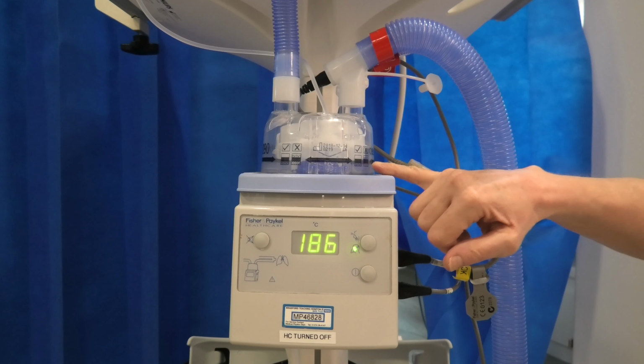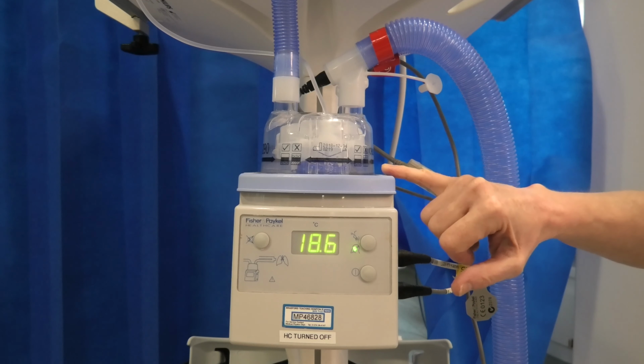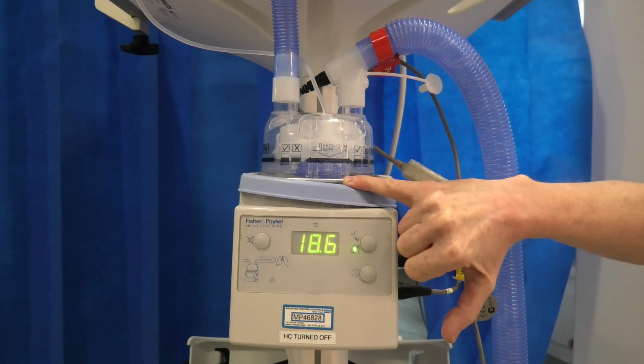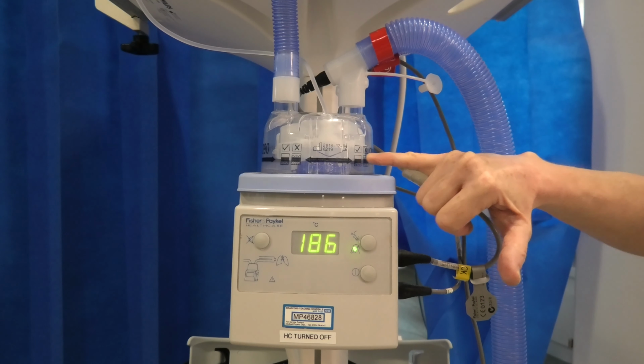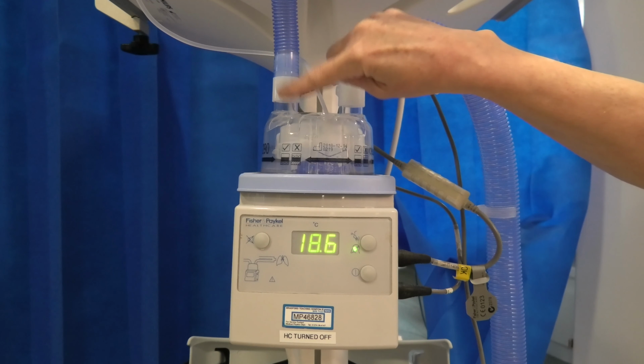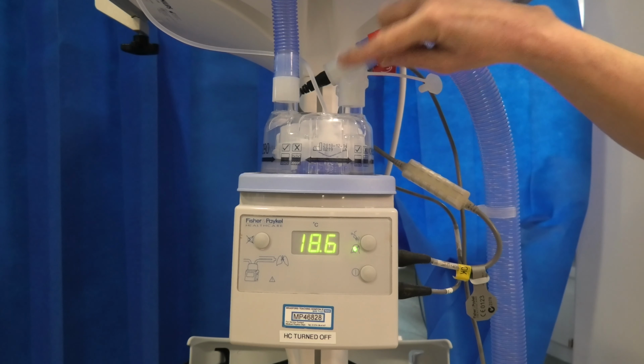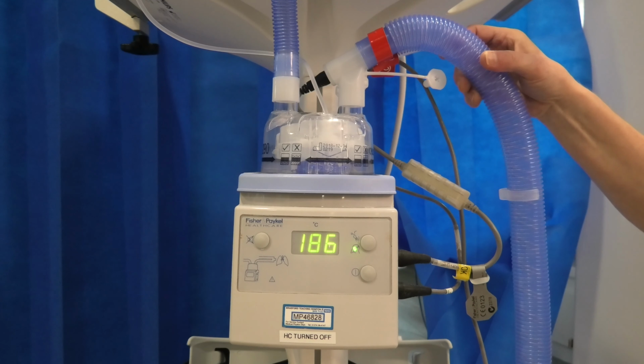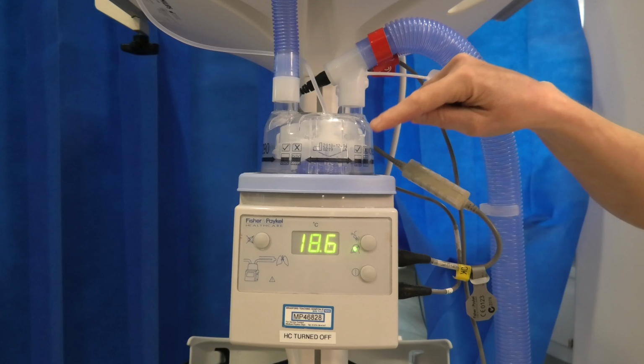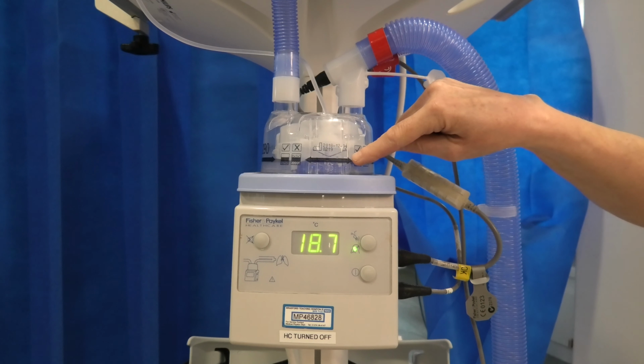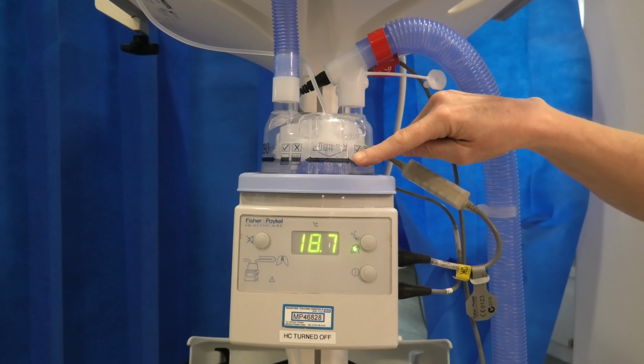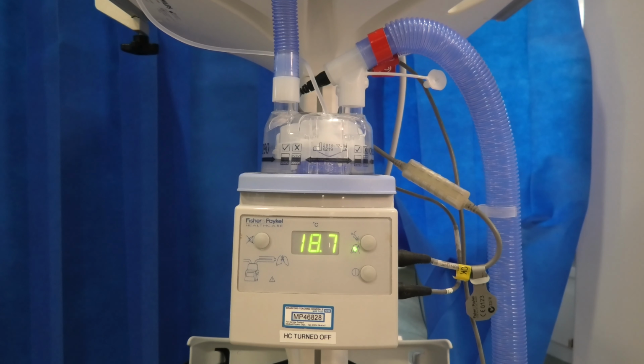It's very important that you've always got water in this chamber, because this plate gets very, very hot, heats up the water, so you've got water vapour that the cold air, oxygen air mix from the ventilator picks up and is carried to the patient via the heated wire. If there's no water in there, that burns. So you need to make sure you've always got a full water bag attached to the Fisher Paykel. It does take a little bit of time to warm up, but not too long.